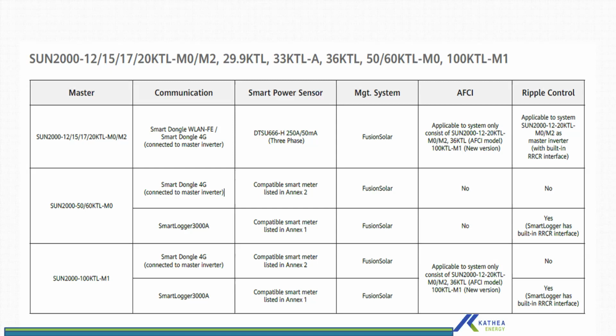And then there is the HUAWEI smart meter, which is the DTSU666-H 250 amp. So when you are using this smart meter, your system is limited to 174 kilowatt, which is equivalent to 250 amps per phase, because the meter comes pre-configured with the CTs. So if you are looking for a larger system, or your incomer breaker is way bigger than 250 amps, then you would need to use the Janitza meter for your grid measurements. However, you can connect a HUAWEI system without a meter if you do not intend to grid limit. But whenever there is an intention to export limit, it's mandatory to connect a meter at the grid incomer.